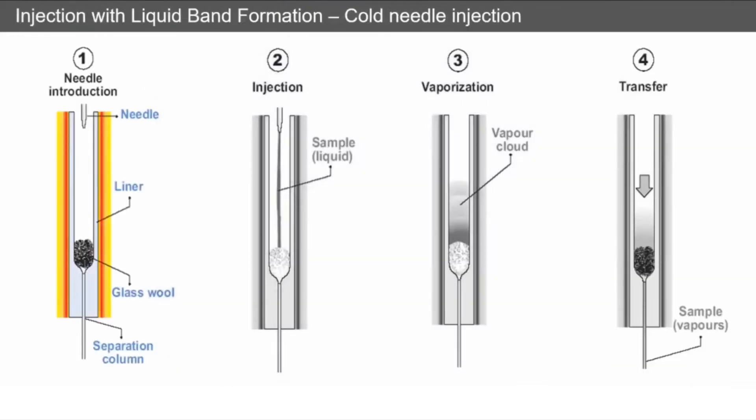For the more traditional cold needle injection, the needle is introduced to the inlet and almost immediately the injection takes place, producing a fine spray of liquid going into your inlet. Typically you'll have some glass wool at the bottom of your liner to stop this liquid going to the bottom, and then a vapor cloud will form by evaporation from the glass wool. This vapor then passes into your GC inlet and onto your separation column.